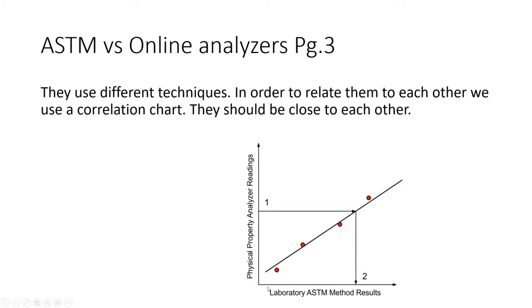There are significant differences technologically, and in terms of accuracy, when we compare lab standards to online analyzers. You can't say they're exactly the same, but they are relatively similar, and we can take our field measurements from online analyzers and compare them to lab standards through a process called correlation. Correlation means we take our laboratory results on one axis and our online analyzer points on another axis.